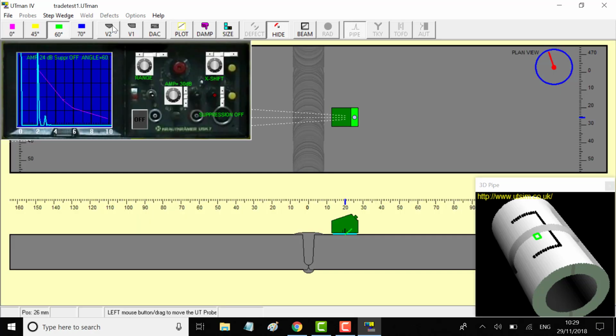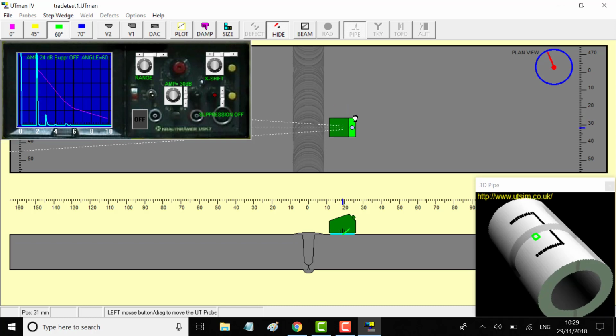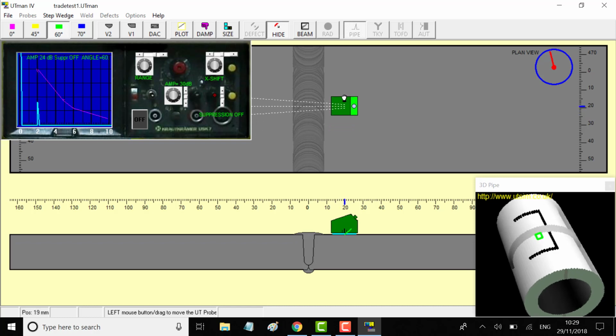And check the amplitude. Amplitude, yep. So now he can find the defect. There's the defect there. We can go to the edge of the defect, which of the 6 dB drop for defect length can be seen here. And it tells us here on the circumference, its position from 0 to 20. It starts at 20.